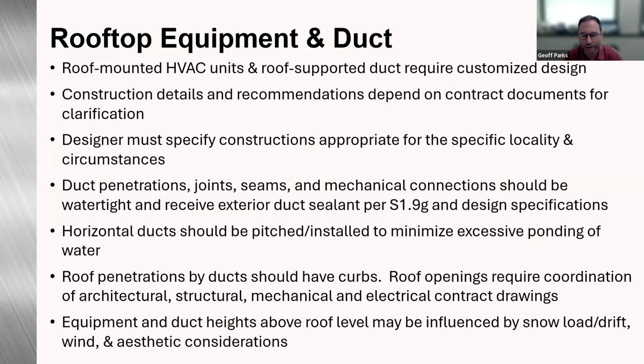And then equipment and duct heights above the roof level may be influenced by snow load, drift, wind, and obviously aesthetic considerations. If you have very wide duct that's high above the roof, you're not going to want to see that over the roof line, over the parapet wall. So, location's going to be critical for aesthetics.